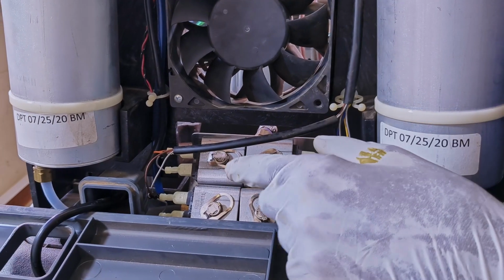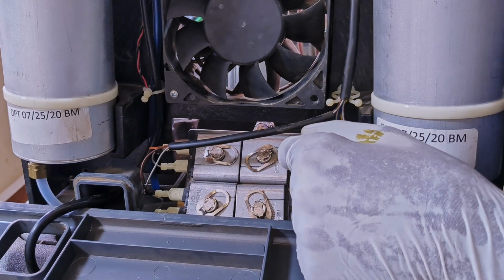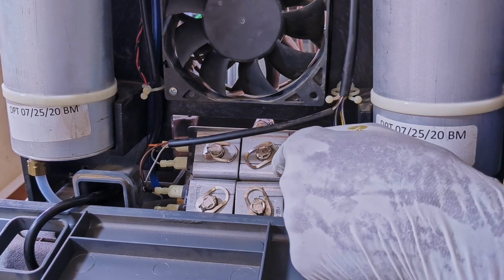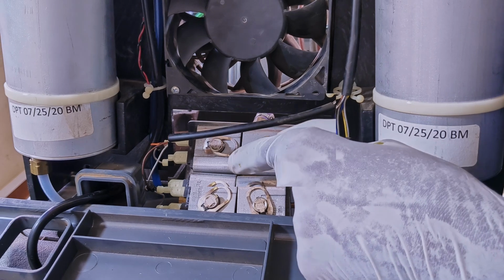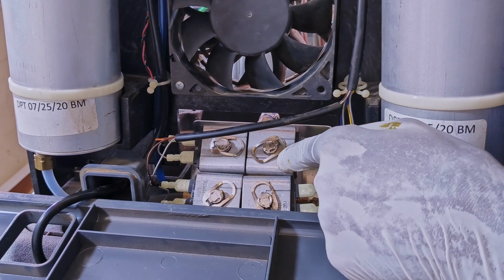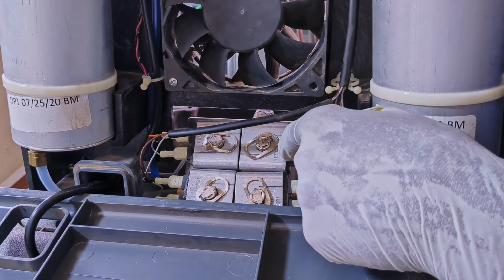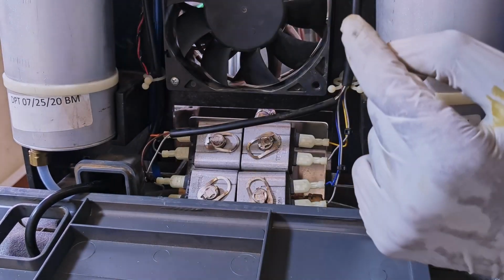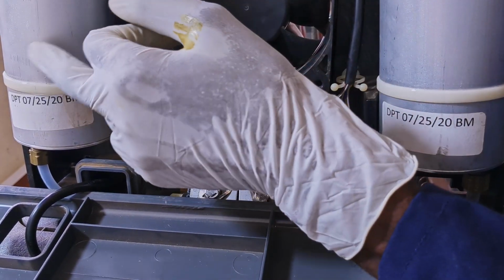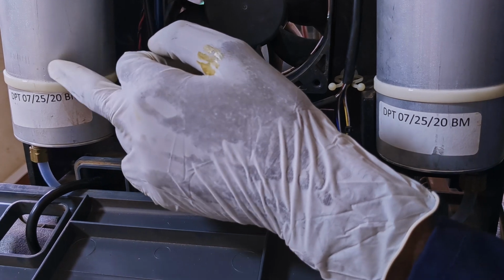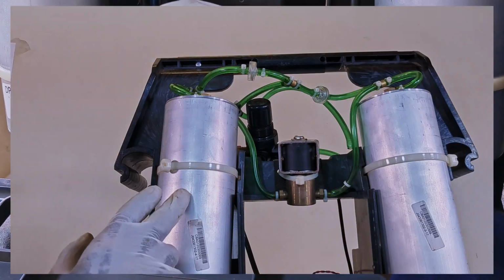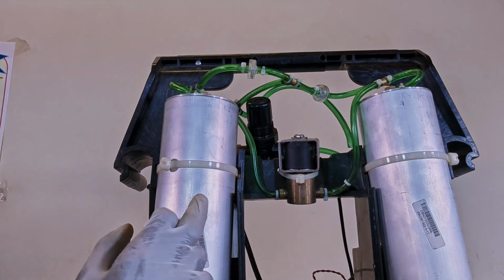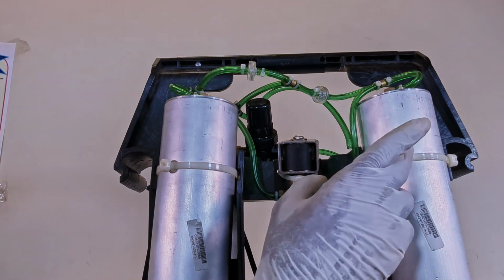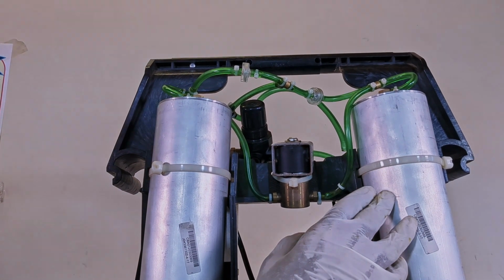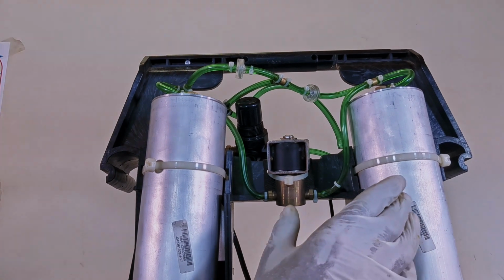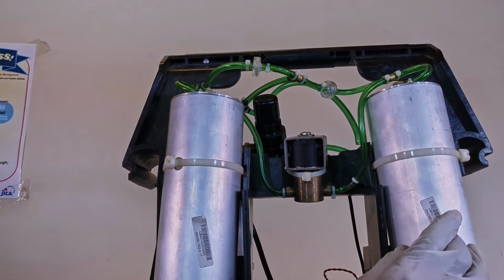From the compressor, air passes to the solenoid valves. So this time around, it is the 2 feed valves that are in operation. These 2 feed valves control the flow of air from the compressor to the sieve beds. Once air is in the sieve bed, nitrogen is separated while oxygen is concentrated. Part of the oxygen produced in the pressurized bed is directed to the depressurized bed, and this helps in the purging of nitrogen in the depressurized sieve bed.